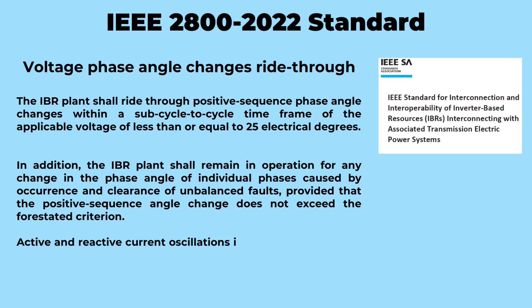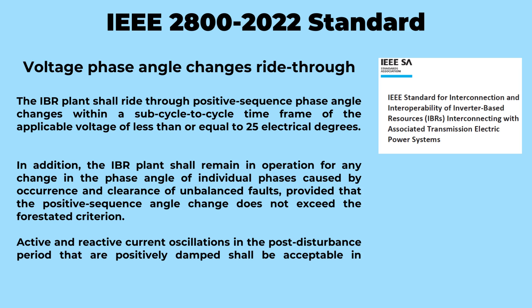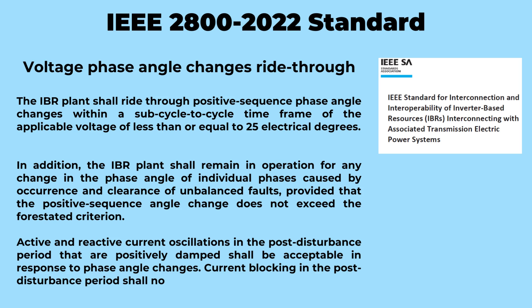In addition, when unbalanced faults occur causing phase angle changes in individual phases, the IBR plant remains steadfast. As long as the positive sequence angle change remains within the specified criterion, the IBR plant continues to power through, ensuring a reliable and stable electrical grid. As phase angles fluctuate post-event, the IBR plant may observe active and reactive current oscillations that dynamically respond to the phase angle changes. These oscillations, being positively damped, signify the IBR plant's ability to navigate through shifting electrical waves. Inverters should not have any scope of current blocking in the post-disturbance period.